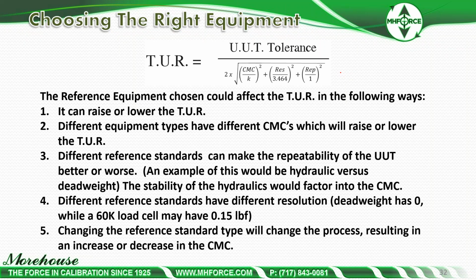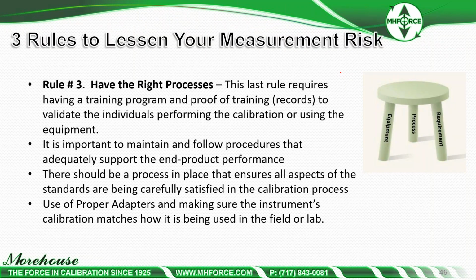Different reference standards have different resolutions. If we're using dead weight, applying masses adjusted for gravity, air density and material density, and we're applying the right masses, then we're going to have 0 resolution, versus a load cell, which could have a resolution of 0.15. Changing the reference standard type will change the process, which will result in an increase or decrease of the CMC uncertainty parameter.